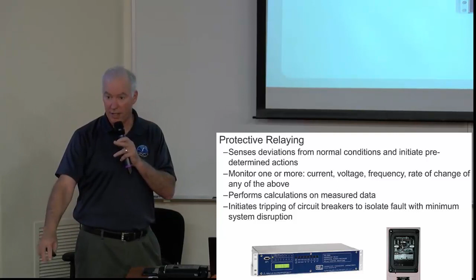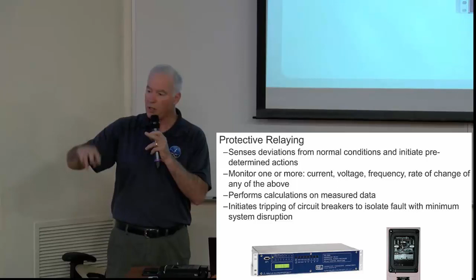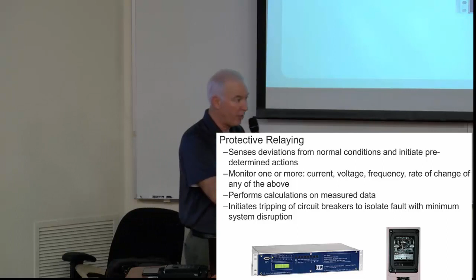Okay, good. So there are relays. When you have a power system, you want the breaker to open that's closest to the fault. So you have to set those relays, you have to do some analysis. You have to go and check what the short circuit current is in the entire power system and make sure the interrupt rating for every one of those breakers can handle it so it doesn't blow up and arc across. That's part of power system design.